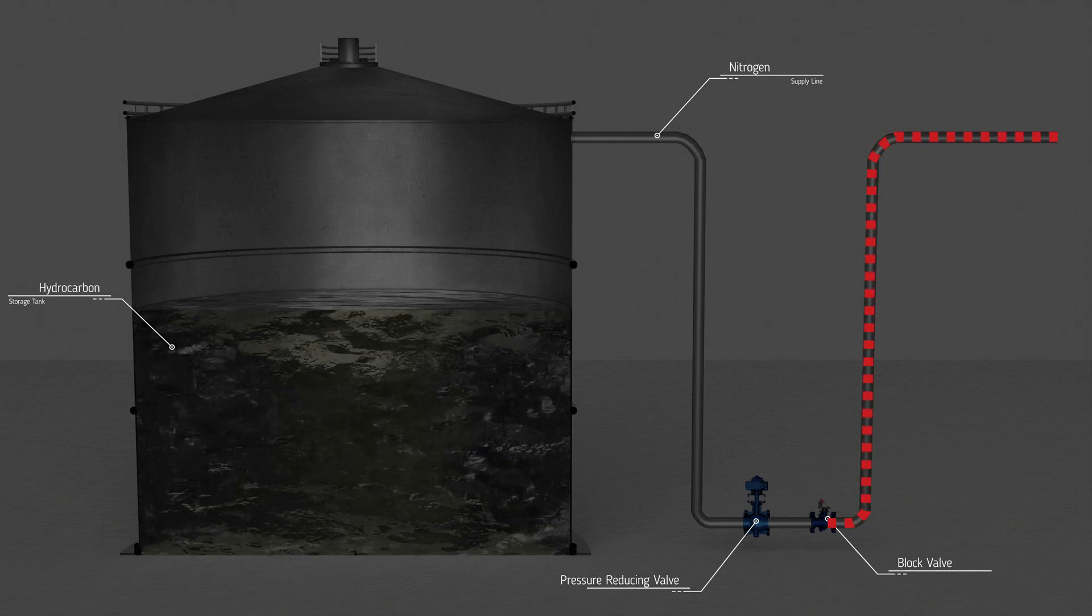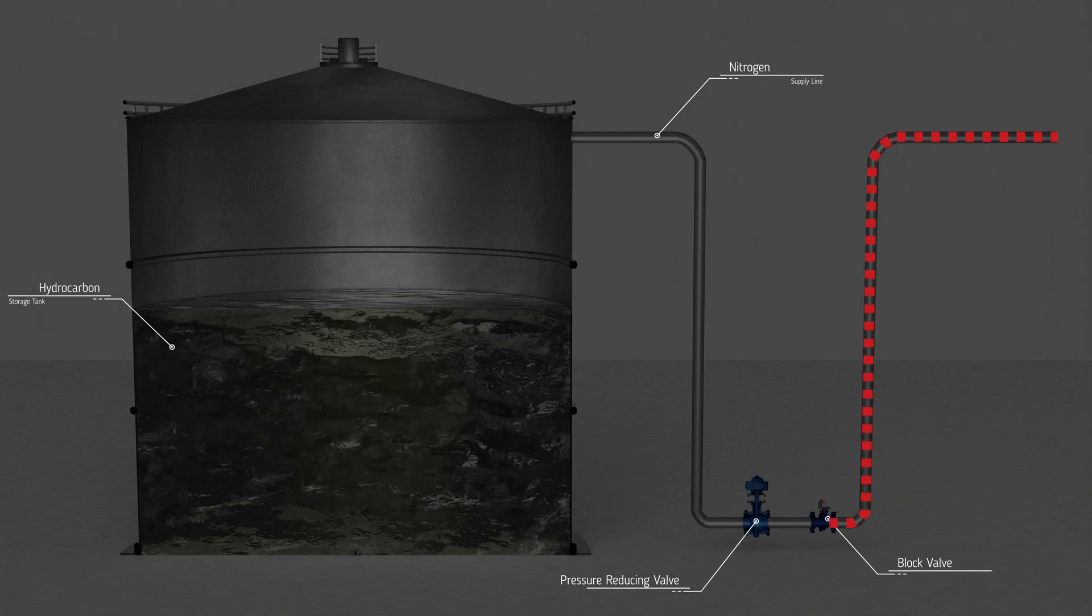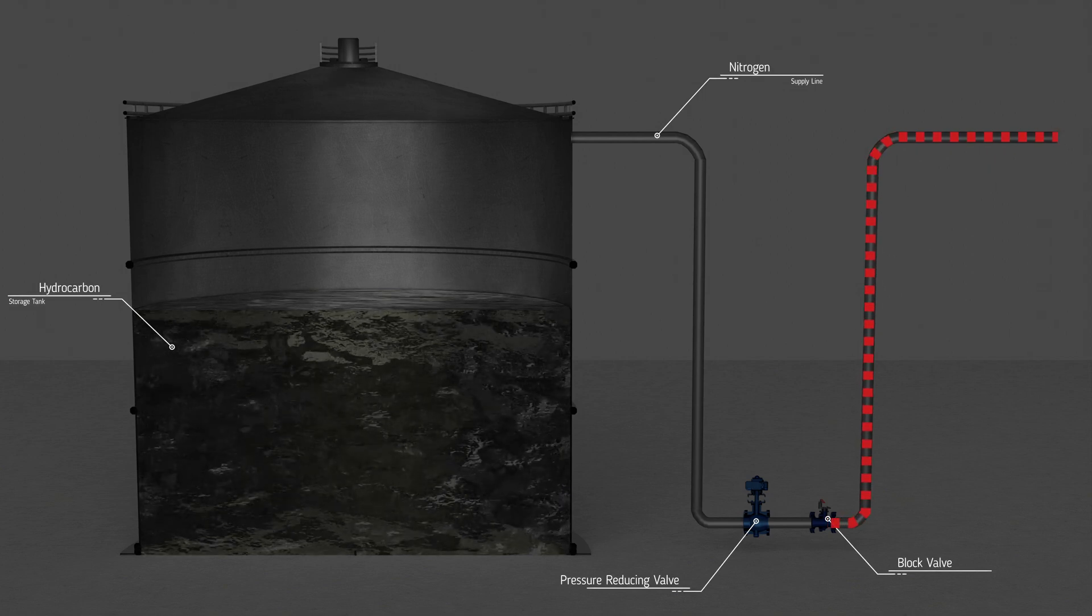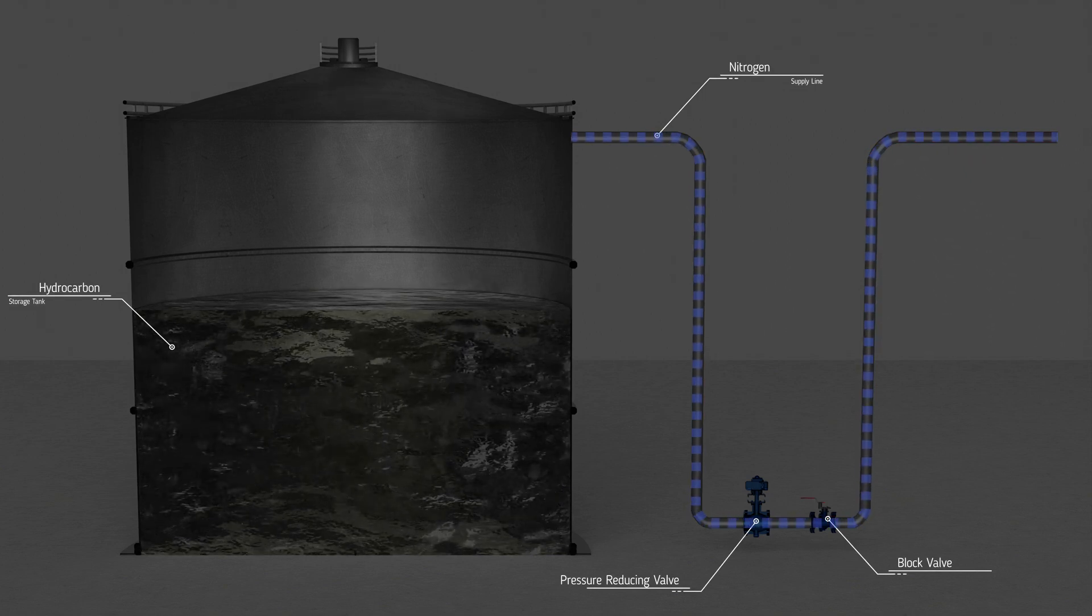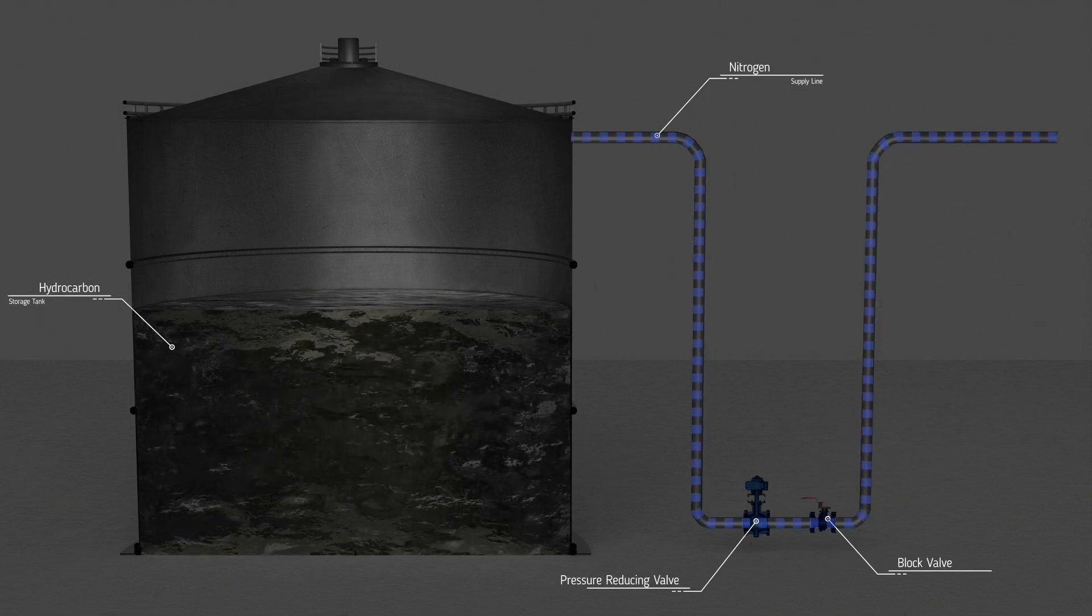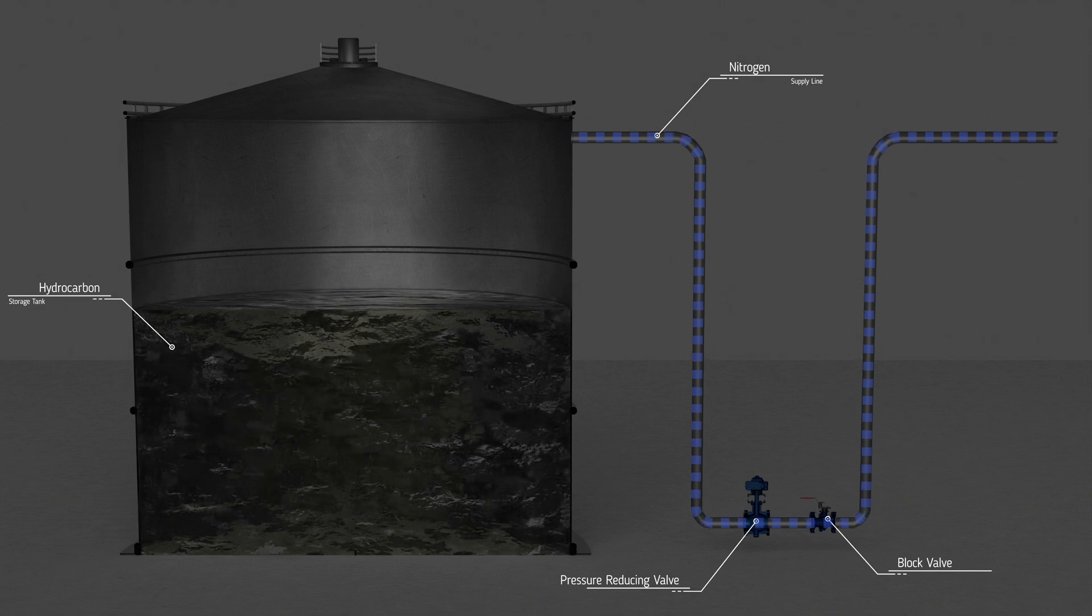All safety equipment and systems should be scheduled for regular inspection and test. Nitrogen blanketing systems should be inspected at least weekly.